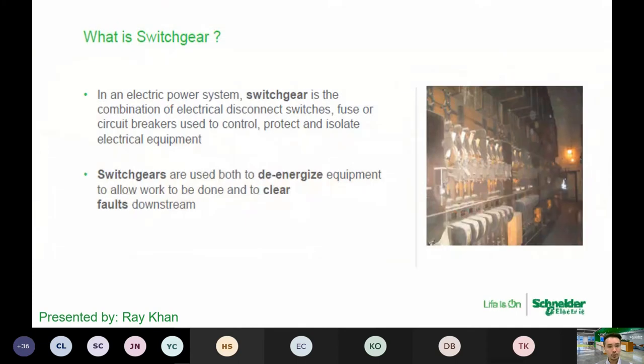Now, for those who are generally new to switchgear, just to give an overview of what switchgear is about. Generally, it's a large circuit breaker and also an isolator. Secondly, it is designed to switch off the power, so it allows work to be carried out downstream. One of the key aspects is that it's designed to clear faults as well. That is why it comes with components, as you can see here, the circuit breaker to control and isolate the electrical equipment, and used to de-energize equipment itself.